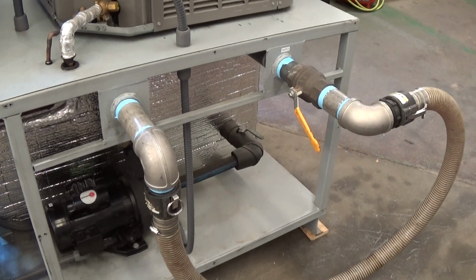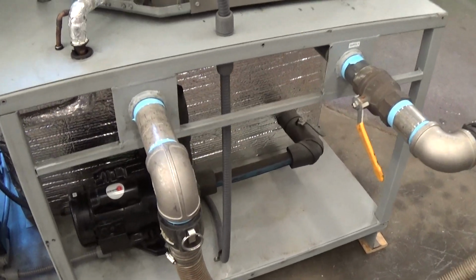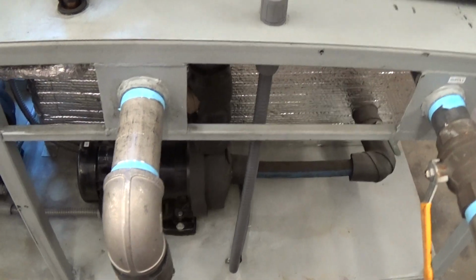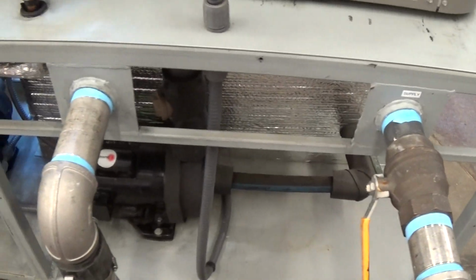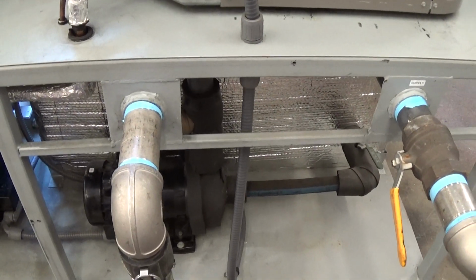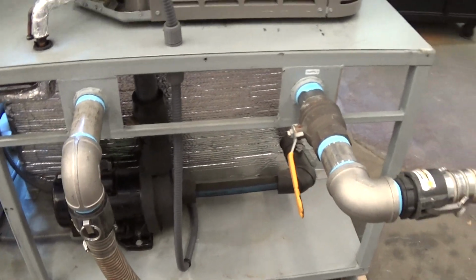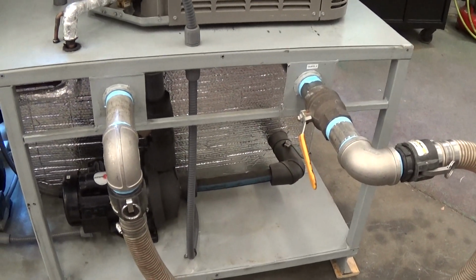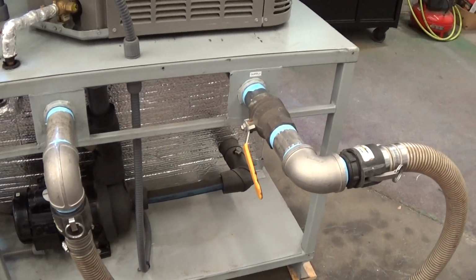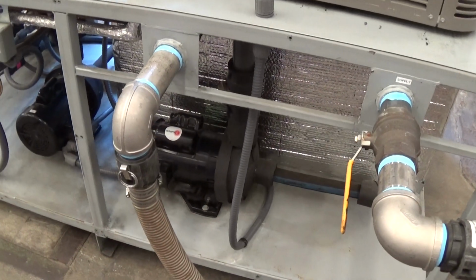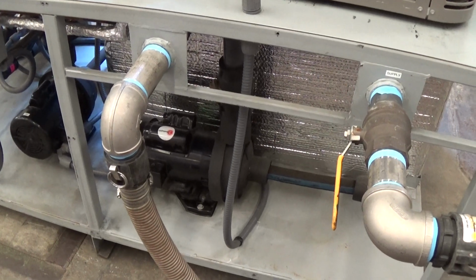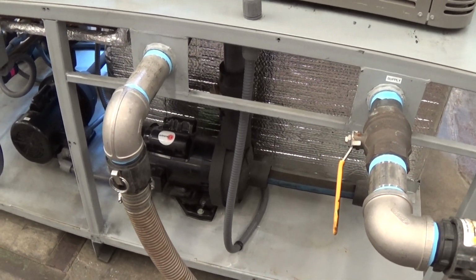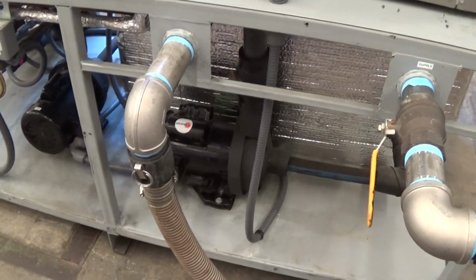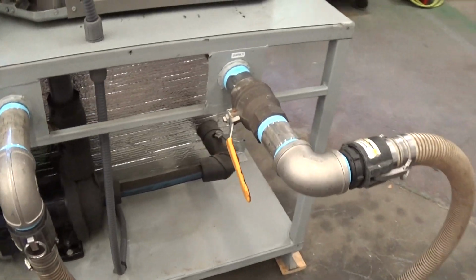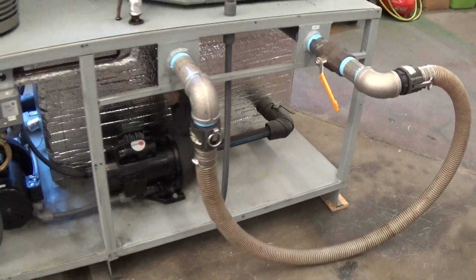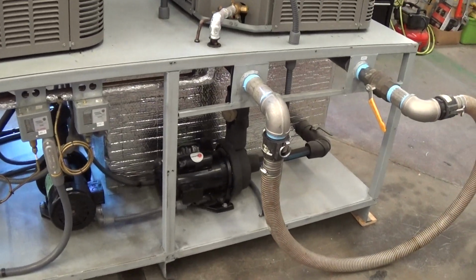In this case, if I was a user, I'd probably just have a small little line from your supply to return. It could be as small as a 1/2 inch with a ball valve on it. So if none of your tanks are calling for cooling, we just have a little bit of flow coming back to the unit, just so the pump doesn't cavitate. You only need a tiny trickle of flow for that pump not to cavitate and burn out. Again, the 2-pump system is really an ideal scenario.